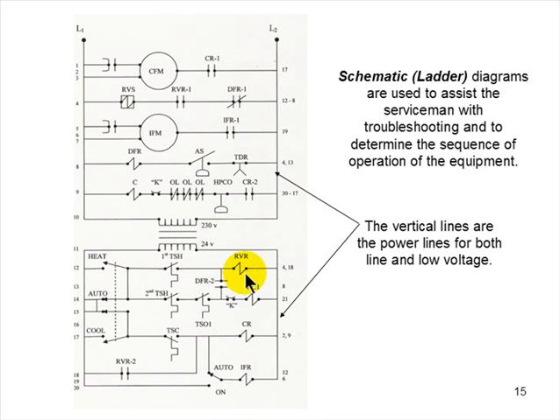Now I can look at this and say, well, here's my reversing valve relay, and it's in series with a thing they're calling 1 TSH. So TS is thermostat, H is heating. The reversing valve is above the line, so it's high temperature, so that makes sense that this thermostat is the first stage heating. Because right down here is a heating thermostat that says 2 TSH, so that's second stage. This is O, so it's probably an outdoor thermostat. Here's a cooling thermostat. So I know my reversing valve by looking at this diagram. If I study it for a minute, I can figure out that the reversing valve is energized in the heating mode. Good information to have if you're dealing with a heat pump.